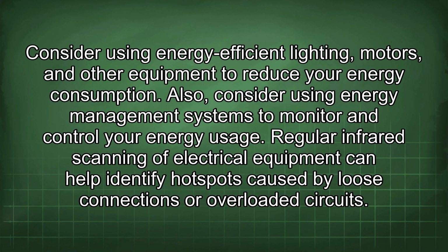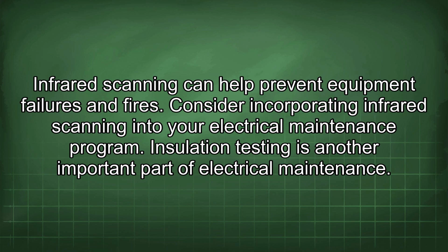Regular infrared scanning of electrical equipment can help identify hotspots caused by loose connections or overloaded circuits. Infrared scanning can help prevent equipment failures and fires. Consider incorporating infrared scanning into your electrical maintenance program.